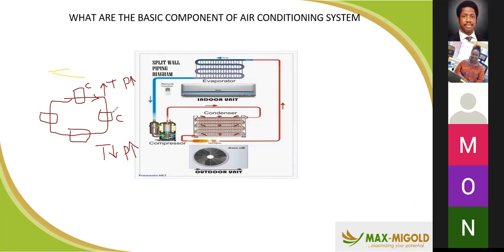Most technicians on site, even some of us, sometimes when our clothes or shoes are wet, we go put them in front of the AC outdoor unit. But that is not good practice, because each time you return hot air into the AC, you are actually killing the compressor. That's why in buildings where you put your outdoor unit, you must have enough ventilation for it. If not, your compressor will die, and if it breaks down, it's the most expensive component after the AC itself.